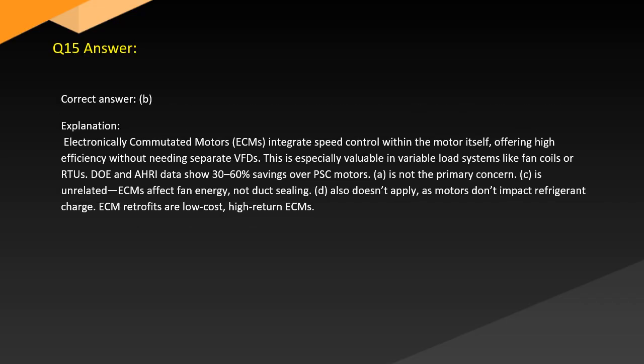Answer. Correct answer: B. Explanation. Electronically commutated motors (ECMs) integrate speed control within the motor itself, offering high efficiency without needing separate VFDs. This is especially valuable in variable load systems like fan coils or RTUs. DOE and AHRI data show 30-60% savings over PSC motors, A is not the primary concern. C is unrelated. ECMs affect fan energy, not duct sealing. D also doesn't apply, as motors don't impact refrigerant charge. ECM retrofits are low-cost, high-return ECMs.